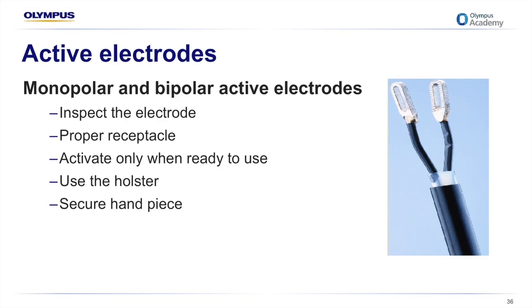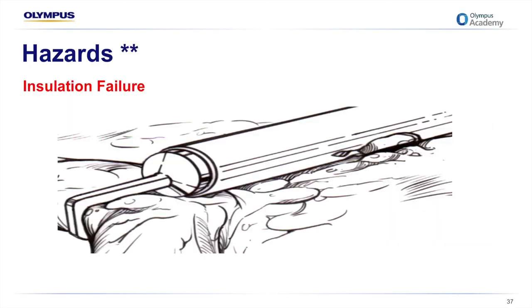In bipolar electrosurgery, one side of the instrument tip is the active electrode and the opposing tip is the return electrode. Care should be taken not to contact the 2 electrodes together and activate the instrument when not grasping. This could result in aberrant current conduction and a potential burn. In monopolar energy, the breakdown of insulation can occur along the shaft of an active electrode. This can allow the energy an opportunity to seek another path of lesser resistance.